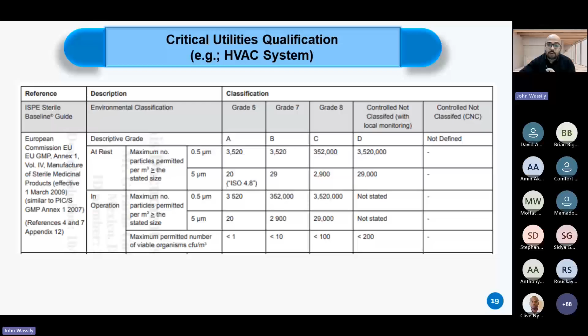Here I'm presenting to you a summary for the HVAC qualification or clean room validation testings that are to be performed in order to say that my HVAC system is fully qualified and is released for operational use. It's not only about performing the particle measurement for the sizes of 0.5 and 5 microns as mentioned on the previous slide. It's also about performing filter integrity testing for the filters that are installed in the clean room itself to make sure that the air is filtered and meeting the cleanliness grades that we are talking about. And here we are listing all the acceptance criteria that we shall meet for every test.